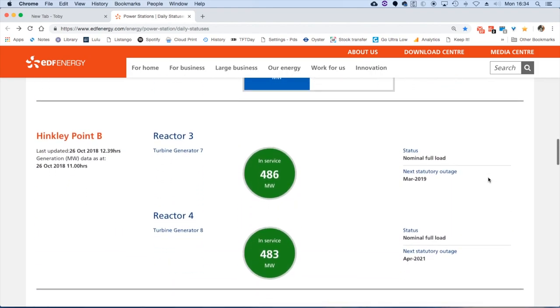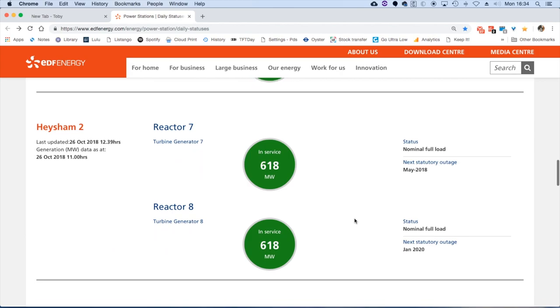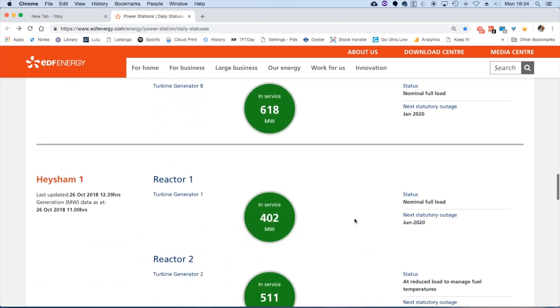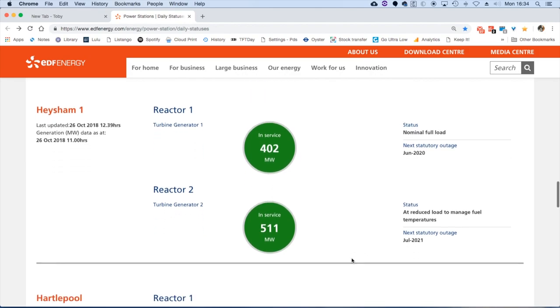Hinkley Point B roughly full. Heysham 2, which is reactor number seven and eight, on full. Heysham 1, and interestingly, nominal full load on reactor one is a little bit low, and reactor two has been showing this error for quite some time at reduced load to manage fuel temperatures.